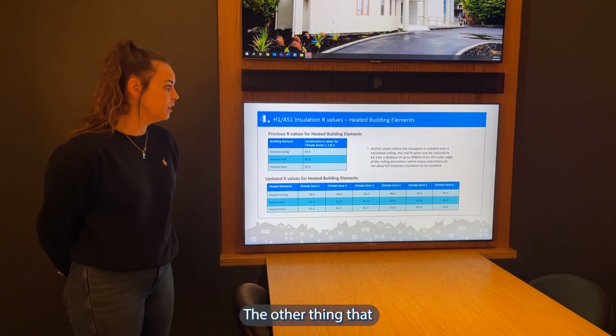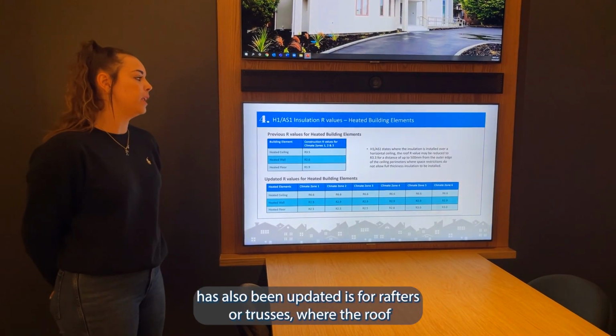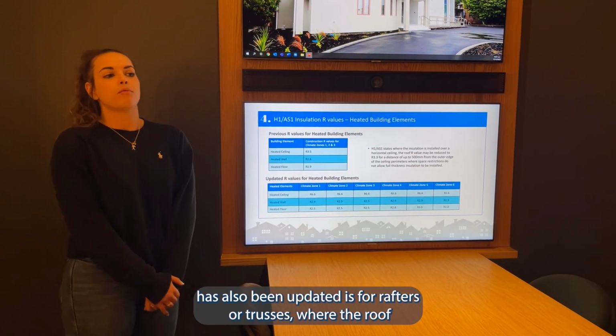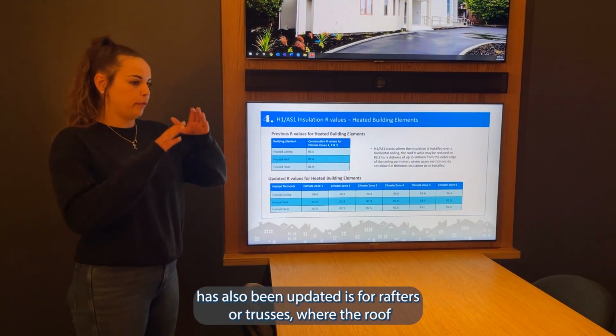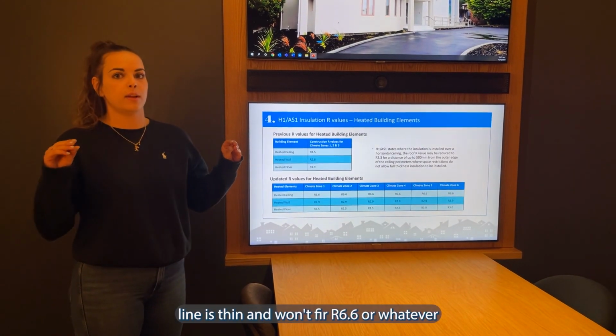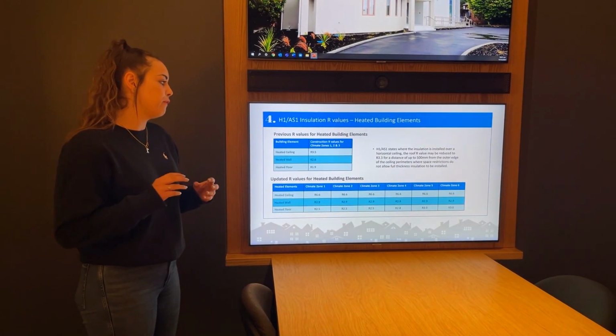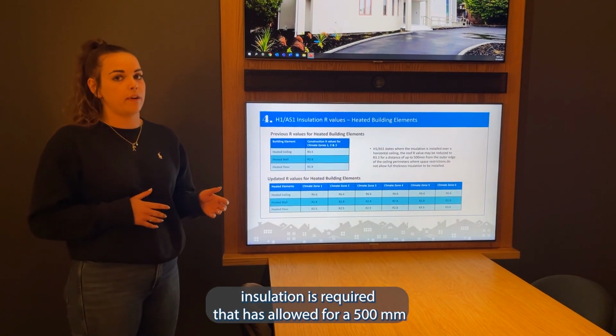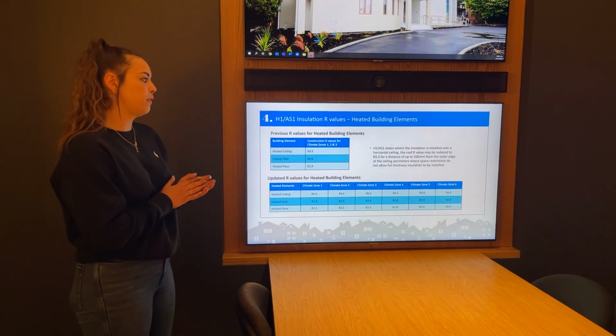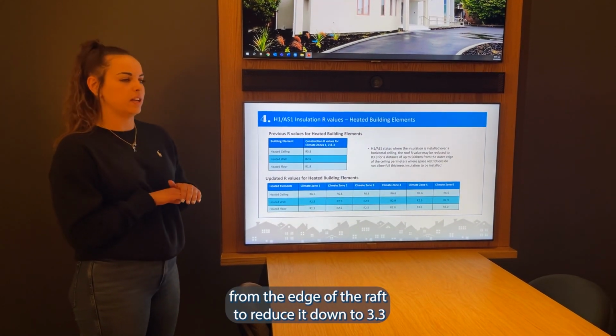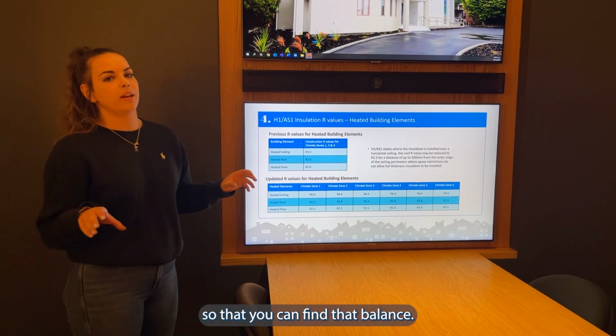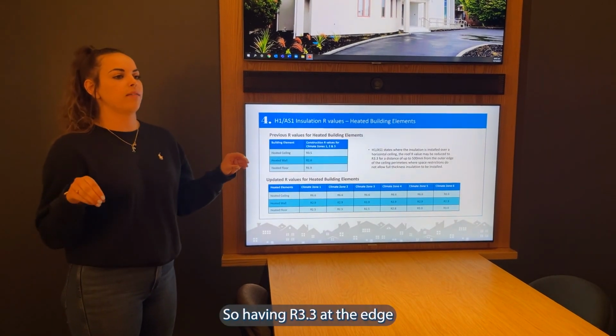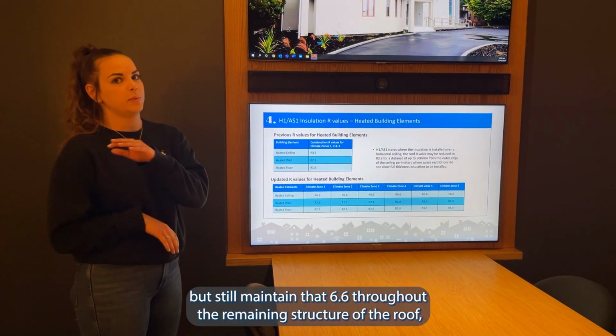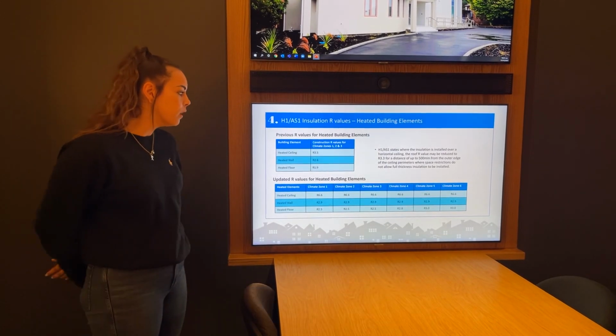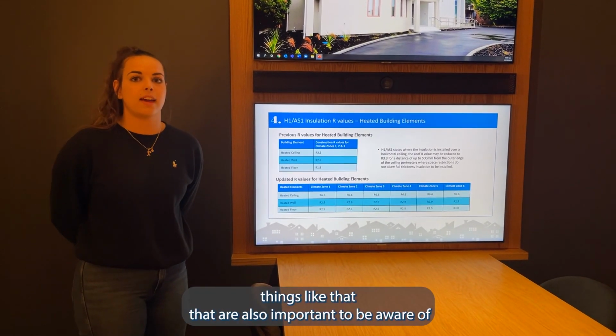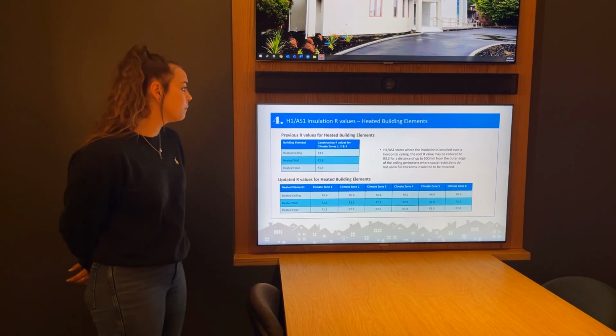And the other thing that has also been updated is for rafters or trusses where the roof line is too thin and won't fit R6.6 or won't fit the insulation required, they have allowed for a 500mm out from the edge of the rafter to reduce it down to 3.3, so that you can find that balance of still having R3.3 at the edge, but still meeting that 6.6 throughout the remaining structure of the roof. So there's a couple of little things like that are also important to be aware of.